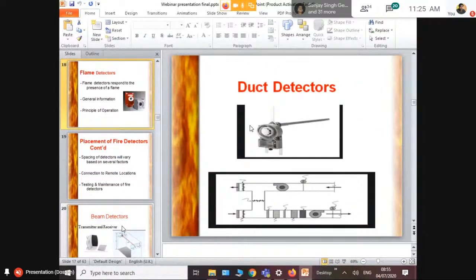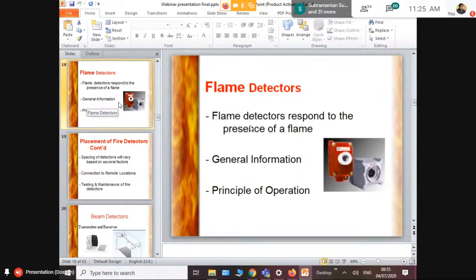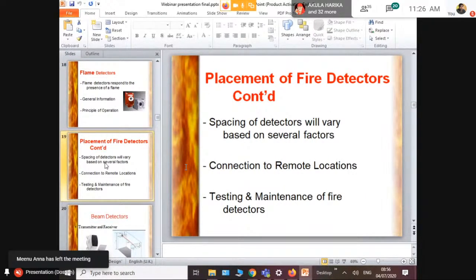Now we have one more detector called flame. It's clear from the name itself: flame detectors. These are detectors installed in areas like oil and gas areas, wherein the type of flames are identified. There are many types of flames, like, in simple words, red, blue, and yellow flames. Each type of flame has different characteristics. In case the characteristics deviate, these flame detectors help you identify it, and a notification will be issued to the control room again. Now we'll see how we place these fire detectors.